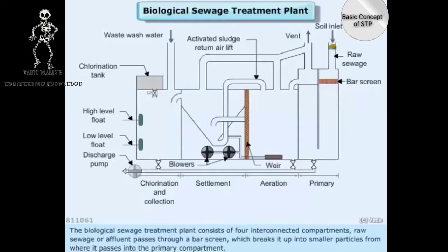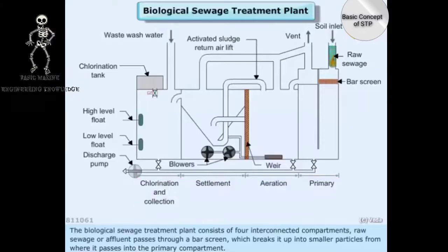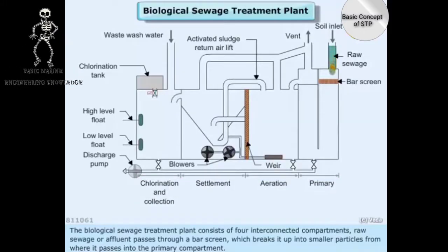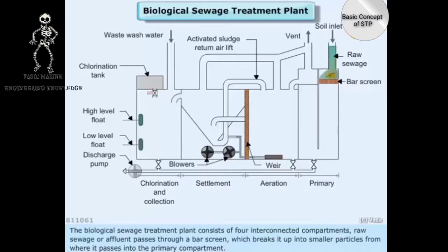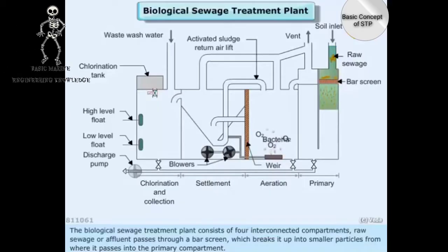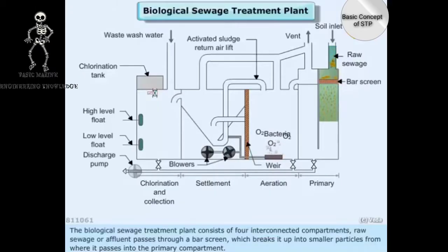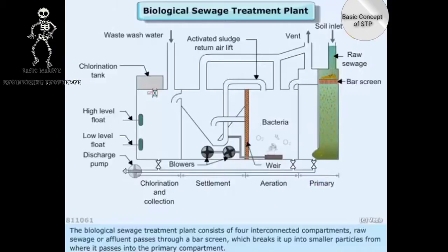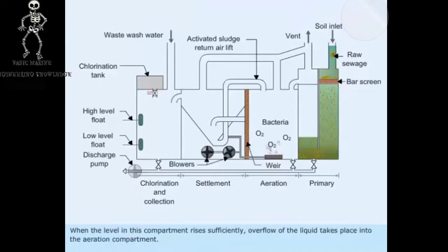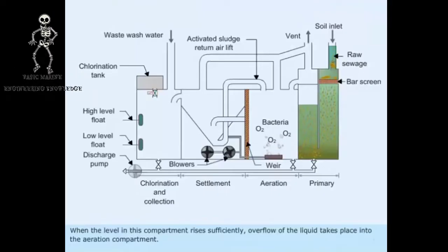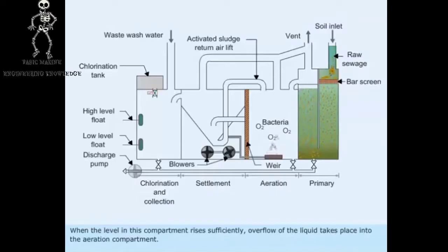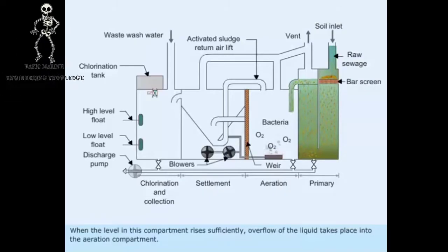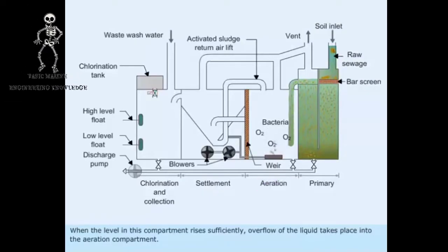The Biological Sewage Treatment Plant consists of four interconnected compartments. Raw sewage or effluent passes through a bar screen, which breaks it up into smaller particles, from where it passes into the primary compartment. When the level in this compartment rises sufficiently, overflow of the liquid takes place into the aeration compartment.